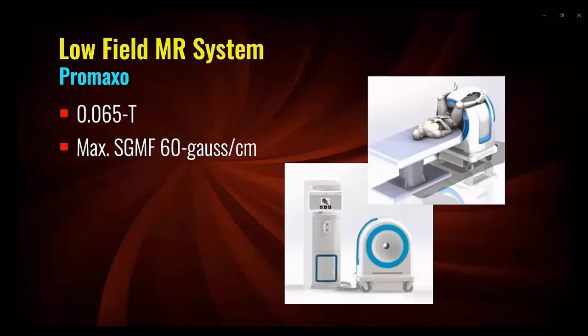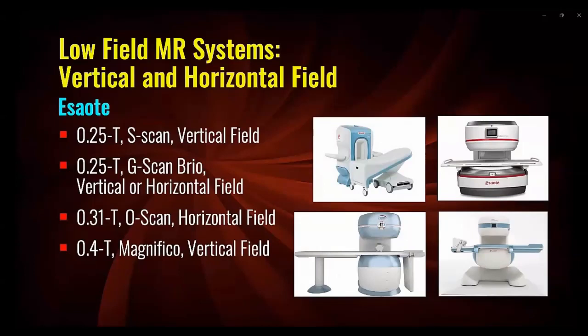Esaote has several low field scanners, including the 0.25 Tesla vertical field S-scan MR system and the 0.25 G-scan Brio. The G-scan has a rotating gantry that permits MRI exams to be performed on the patient's musculoskeletal system during weight bearing. Esaote also makes the dedicated extremity O-scan system, operating with a horizontal magnetic field of 0.31 Tesla, and finally the 0.4 Tesla Magnifico scanner, which also has a vertical magnetic field.